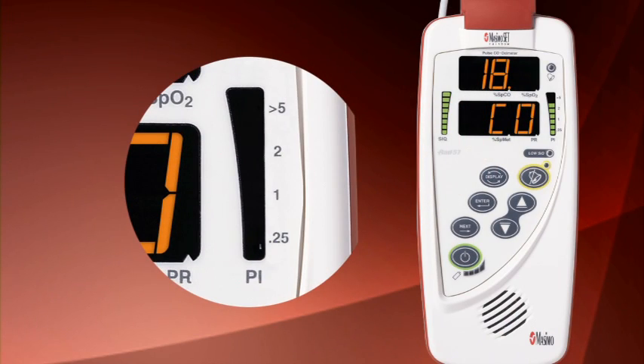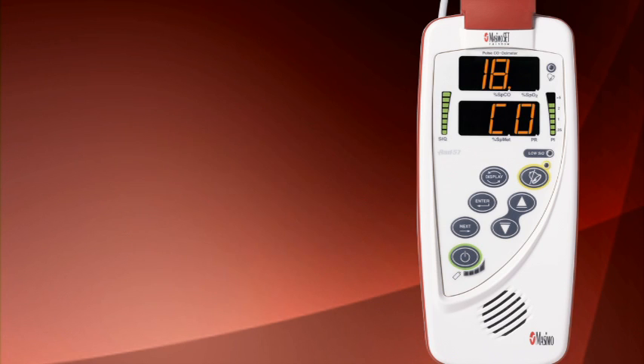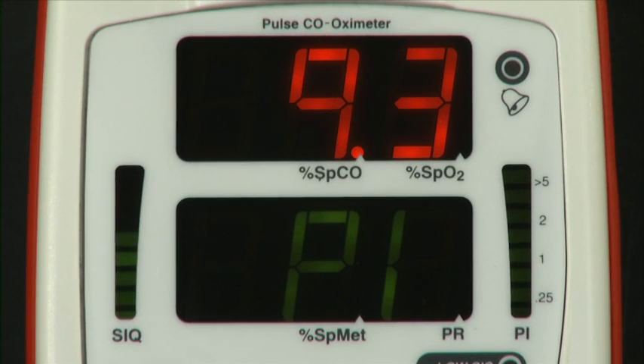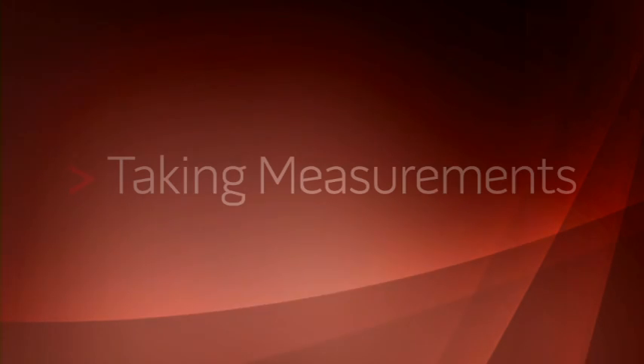The bar to the right of the LED display is the PI bar. The perfusion index, or PI, represents the peripheral perfusion of the digit that the sensor is applied to. Each patient will read differently. Warm hands will tend to read higher, while cold hands tend to read lower. The PI value will also be displayed numerically on the display screen in addition to the LED bar graph. This is the factory default. You can elect to turn off the numerical display, leaving only the PI bar graph. Instructions for turning the numerical PI display off can be found in the operator's manual.